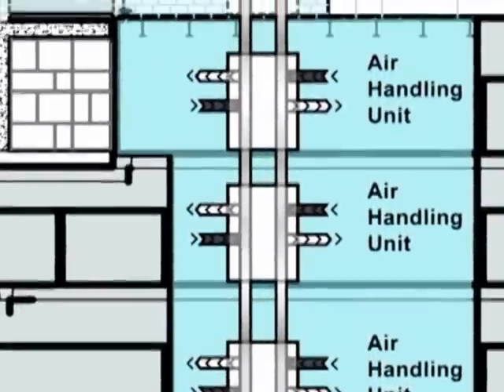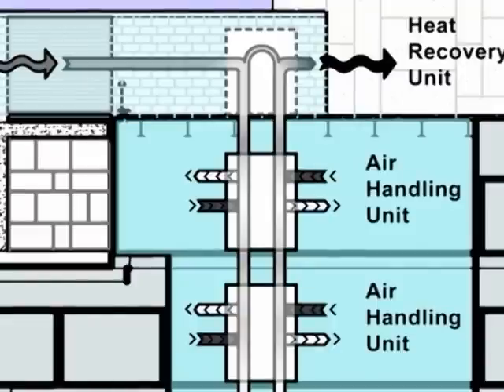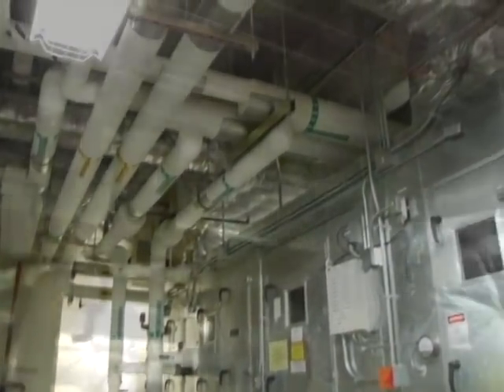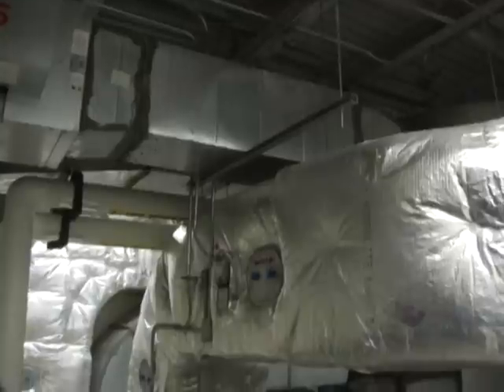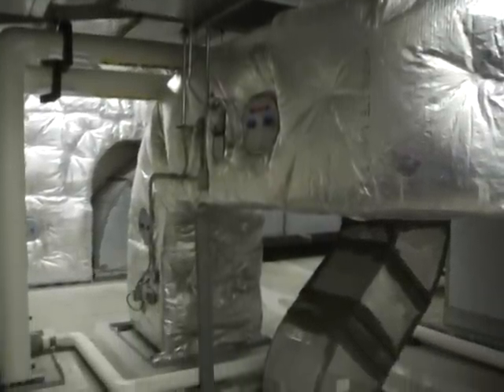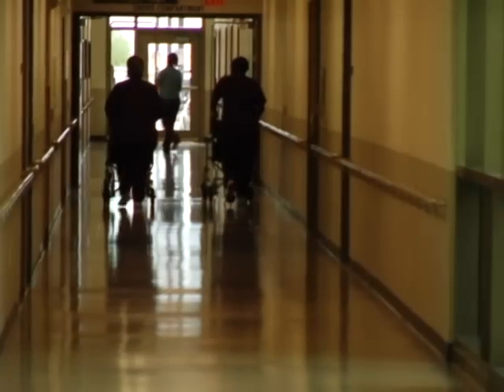Units were stacked on a floor-to-floor basis or placed in close proximity so that chilled water and heating water distribution requires minimal pipe runs. Ductwork was designed with low velocities and low friction losses to maximize energy performance in the distribution system, which yielded energy savings through smaller fan motors. Many energy efficiency improvements yield short payback periods and return on investment, and offer significant savings in operations and maintenance costs — money that every hospital would prefer to direct to mission-critical priorities.